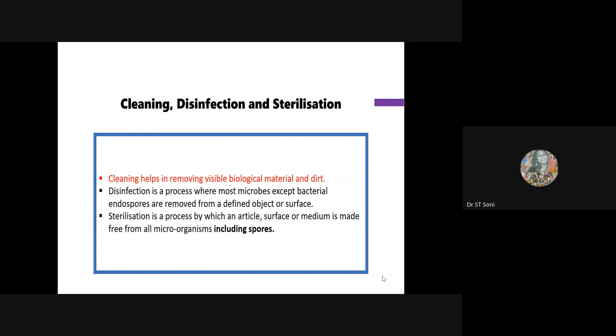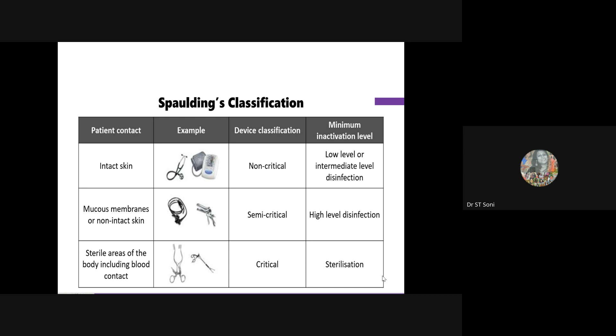Okay, so Spaulding's classification is applicable to it. When we are dealing with an instrument, if it is non-critical, you can use a low level disinfectant, like for the BP instrument and oximeter and all. If it is going to your mucous membrane, like any of the scopes, it is semi-critical, high level disinfection, and it's better to use sterilization. And third is the critical, if it is going into major body cavities, body vessels, including blood contact, then it has to be sterile. Okay, so this is what CSSD is. When you do all this activity, we need to validate our activities. So it's very important to put in the controls.